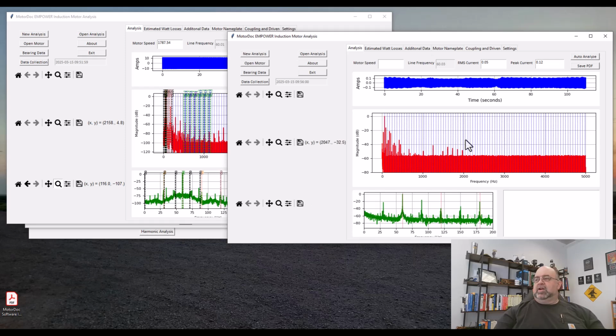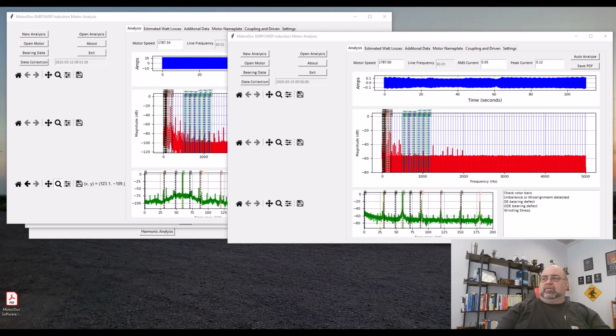So let's go ahead and we'll run that auto analyze. But you know, technically, if I were to just pick this up and look at it, I'd go, okay, it looks similar, but this very high raised noise floor, that is something specific. Now we're going to go ahead and run that, so I'll show you what it picks up and thinks the speed is. There should be no change in speed. Okay, so without doing anything, just letting it run. So I've got 1787.54. That's the accurate speed from a direct current signature analysis measurement. This is from what's sitting on the surface just from placing the CT against the side.